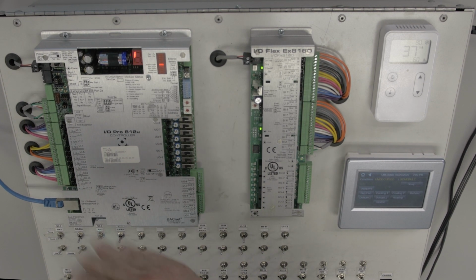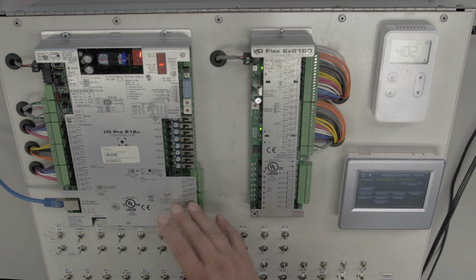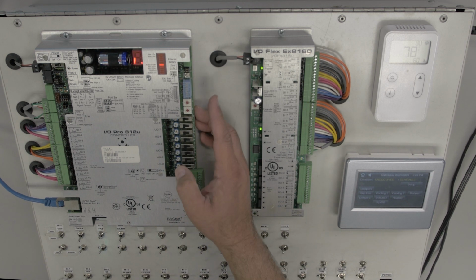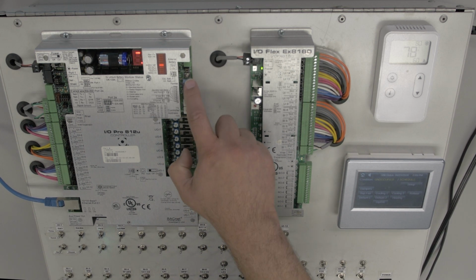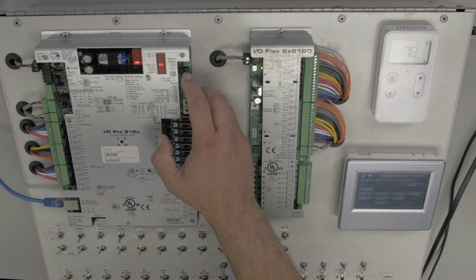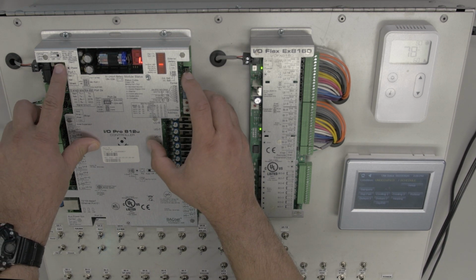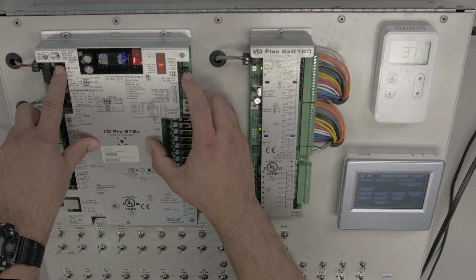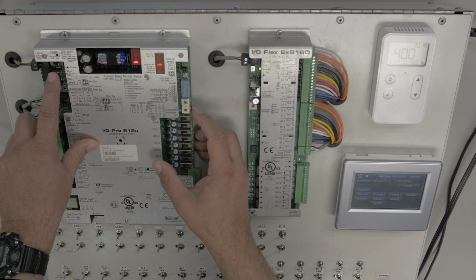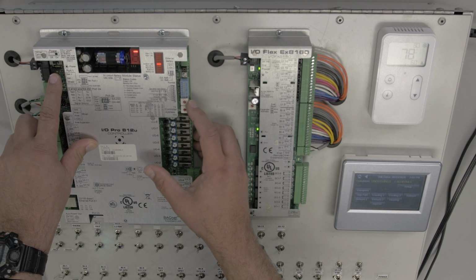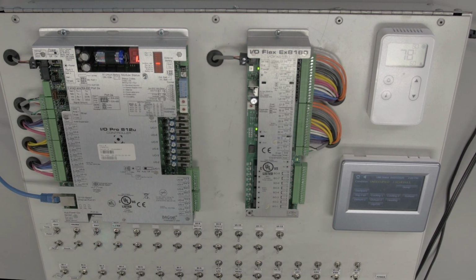Disconnect any building automation system that's connected to the unit, and then while the power is off, with your right index finger, press and hold down the little white button there called the format button. While you're holding it down, turn the power onto the controller and count to 60 seconds. After the 60 seconds has elapsed, turn the power off, release the button, turn the rotary dials back to 0 on the bottom, 2 on the top, and your board will have been restored.